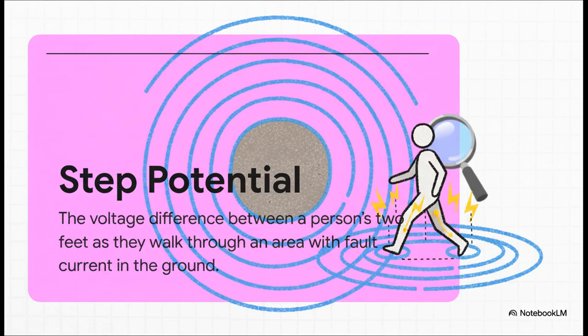All right, now for the second hazard, step potential. This one's a little weird, not as obvious. When that fault current hits the earth, think of it like dropping a rock in a pond. It creates these invisible ripples of voltage spreading out. Now if you take a step, your two feet land on two different ripples, and because they're on different ripples, there's a voltage difference between your feet. That's the step potential, and it can drive a nasty current right up one leg and down the other.